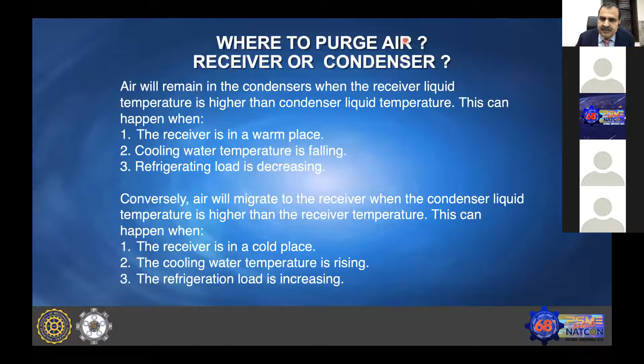Typically, you should not take the air purger purging point from the inlet of the condenser, which should be from the outlet of the condenser. For the receiver, it should not be very close to the liquid entry into the receiver. It should be taken from the furthest point, because if any flash gas is entering into the system, at the end of the receiver the velocity of this gas will be low, and you will be able to take out the air.